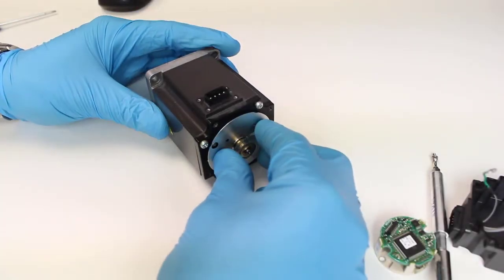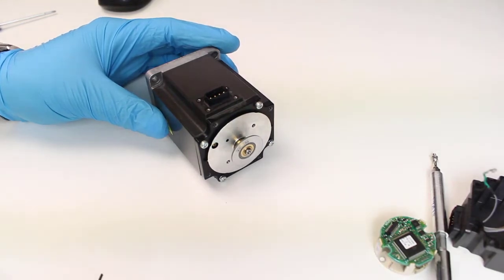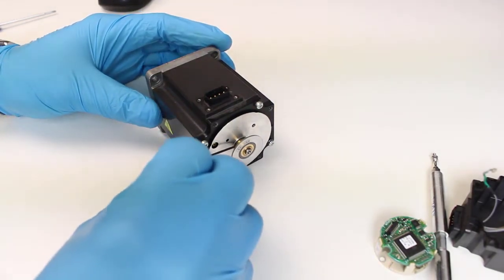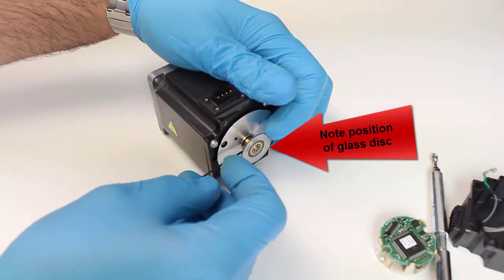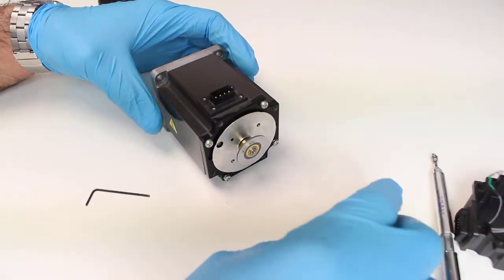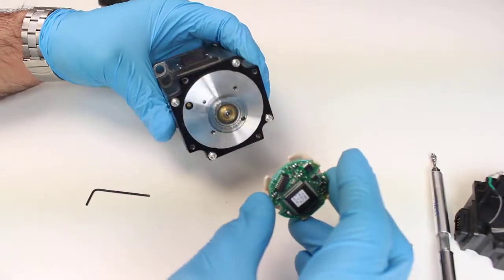To install and align the encoder, first install the glass disc. Insert a set screw to help keep temporary position. Make sure to set the linear distance of the disc as noted previously. Then fully install the encoder sensor.